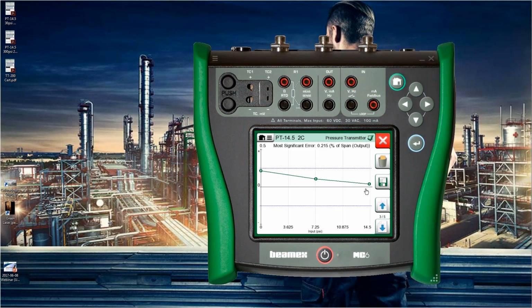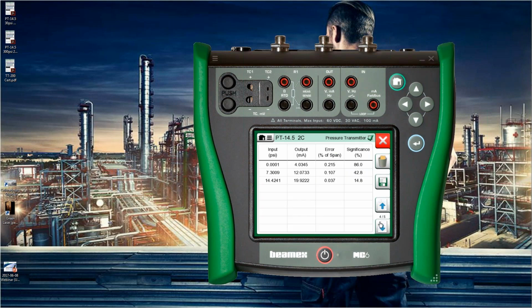The graph itself is here. The blue lines represent my tolerance, and this test actually passed. It's within the blue bands, which means it's within our tolerance. So let me go down again. I didn't specify what my tolerance was, but my maximum error allowed was set to 0.25% of span. So the very first one was the farthest out. The zero is pretty far out on this transmitter.